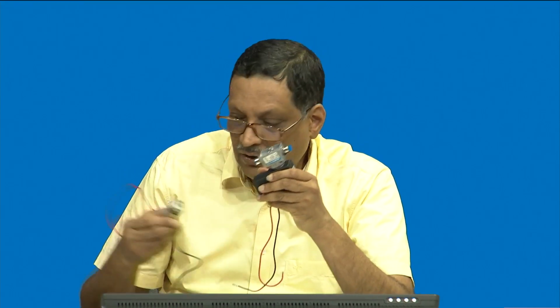So all of this is what you will have to take care of. Remember, your IoT node may not give you 24 volts, it will work with 3.3 volts. The solenoid valve only needs a command coming from your IoT node, but the valve itself operates at 24 volts. So you connect it to another power supply which can give you 24 volts, and that will take care of the power requirements for the solenoid valve.